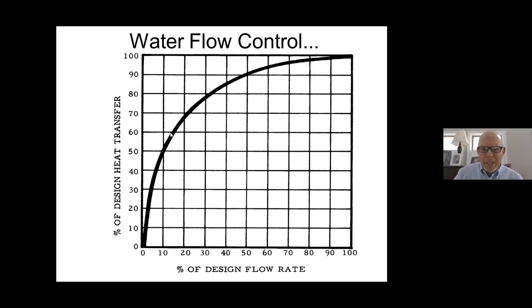You already know this if you look at baseboard manufacturers' literature — they show heat output based on water temperature. Designed around 180 degrees, at one gallon per minute you get around 580 BTUs per linear foot, and at four gallons per minute you only pick up about 30 more BTUs per linear foot. So flow has the least impact on heat transfer. There are three elements: surface area of the heat exchanger, the temperature difference between the water and the air, and flow rate. Flow rate has the least impact — that's why hydronics is so forgiving.